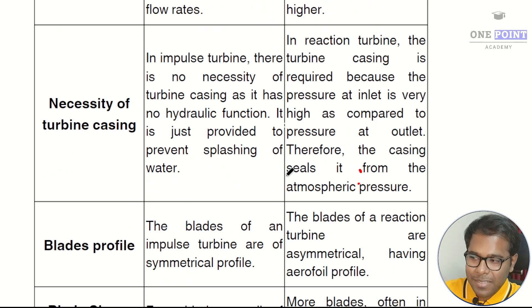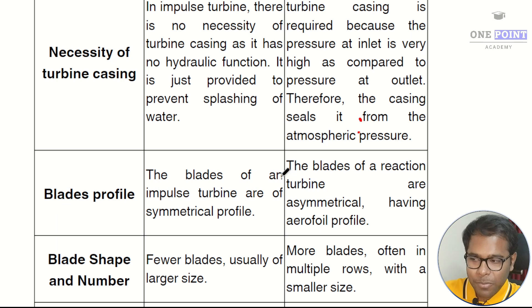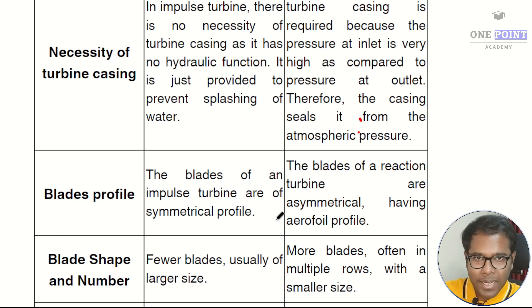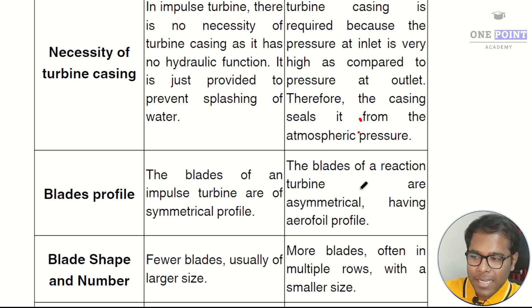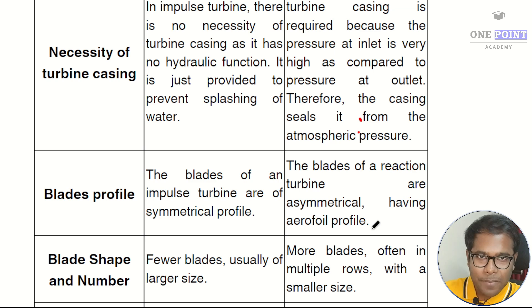The next difference is based on blade profiles. The blades of an impulse turbine are of symmetrical profile, also known as semi-ellipsoidal bucket type, whereas the blades of a reaction turbine are asymmetrical having an aerofoil profile — similar to the profile of an airplane wing.